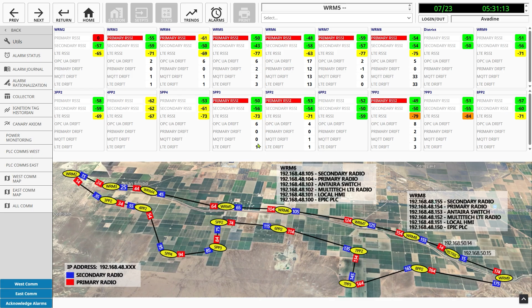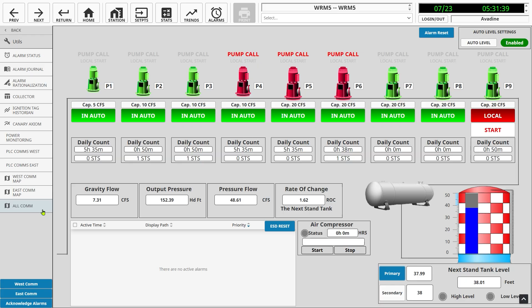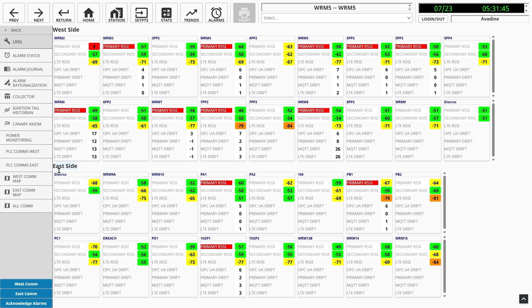Because we pulled them into the Node-RED in the PLC, it became super easy to just transfer that data into a tag in my PAC Control. Now it's a tag, and I can historize that tag. Now I can start to set some warnings if we're seeing issues here because RSSI has changed by some threshold. So leveraging Node-RED on the Epic PLC became very impactful.